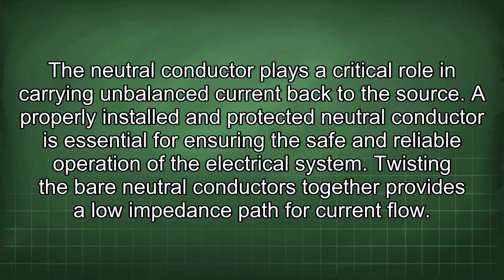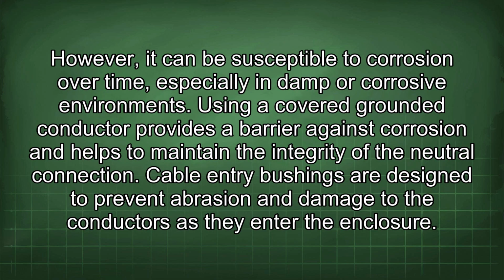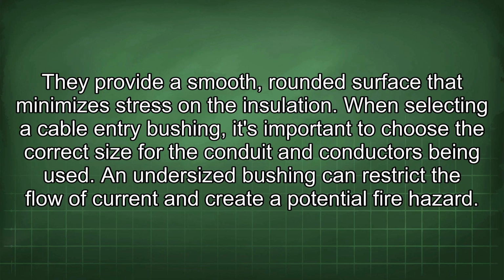Twisting the bare neutral conductors together provides a low impedance path for current flow. However, it can be susceptible to corrosion over time, especially in damp or corrosive environments. Using a covered grounded conductor provides a barrier against corrosion and helps to maintain the integrity of the neutral connection. Cable entry bushings are designed to prevent abrasion and damage to the conductors as they enter the enclosure. They provide a smooth, rounded surface that minimizes stress on the insulation.